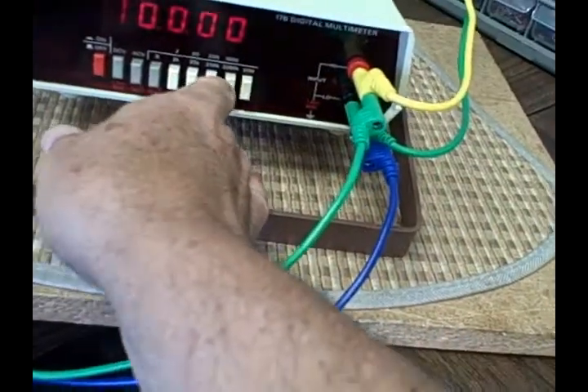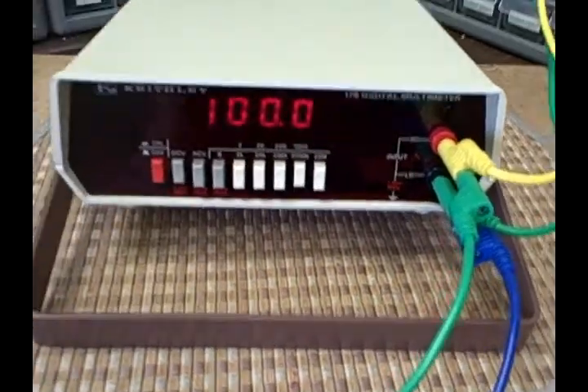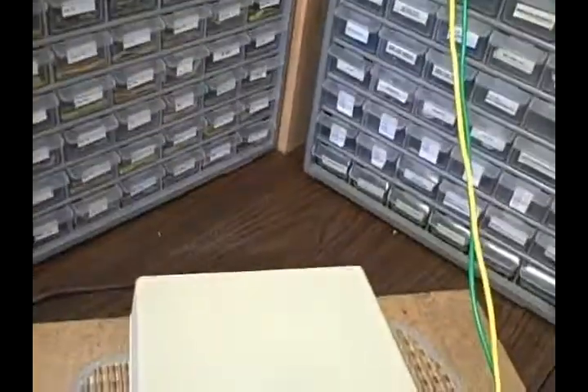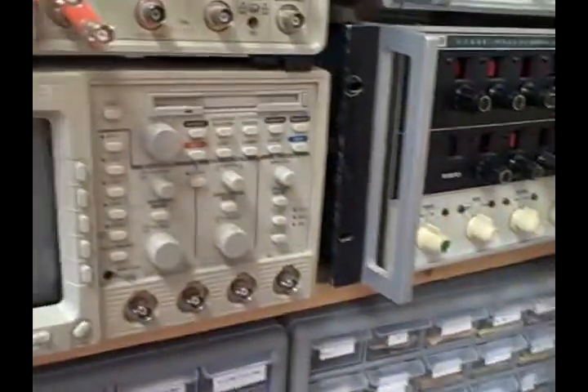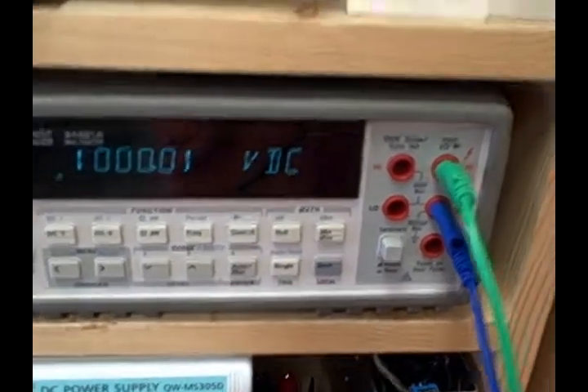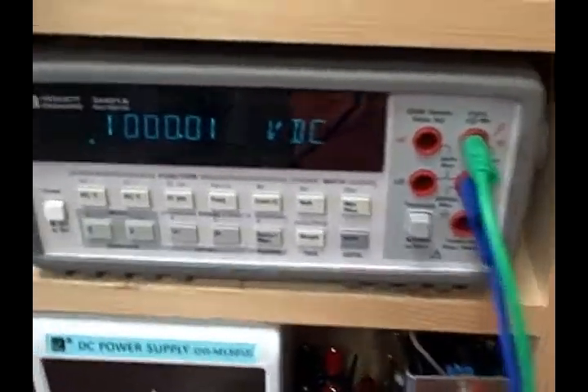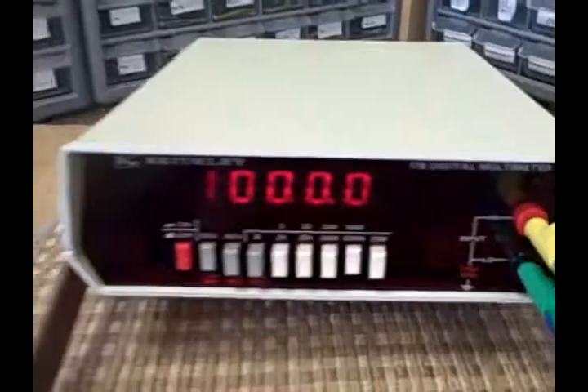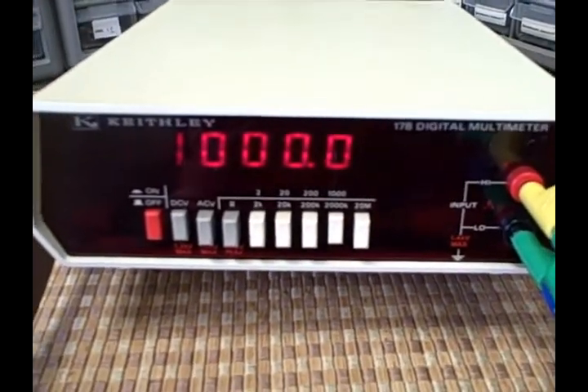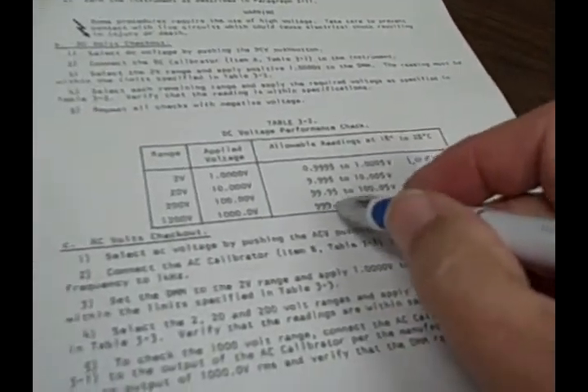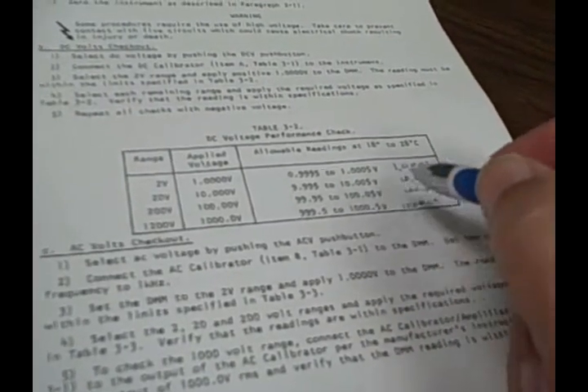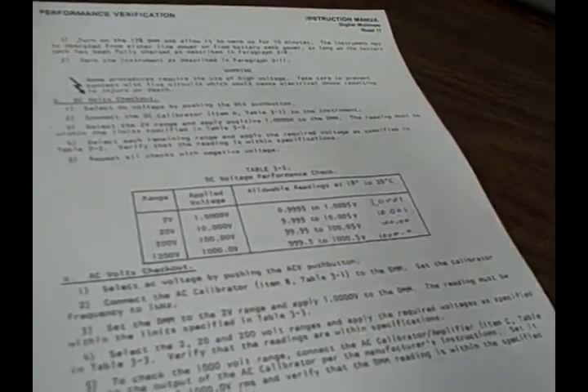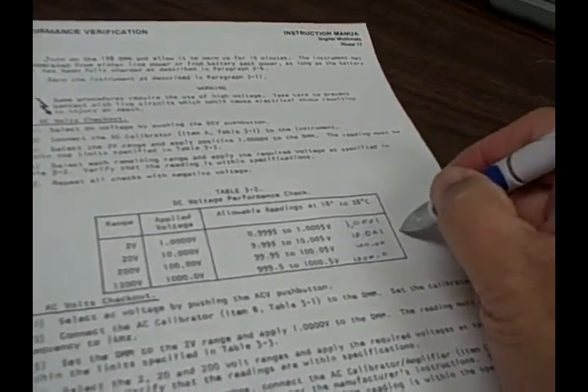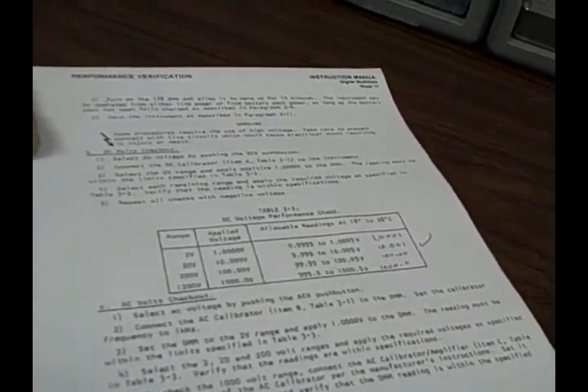Let's go to the 1000 volt scale. We have 100 volts, that's good. And we're going to take ourselves up to 1000 volts. 1000.01 on the HP. 1000.0 on the Keithley. So 1000.0, perfect. We're good if we read between 999.5 to 1000.5, and we were right on it. So we passed the DC performance check beautifully. Let's move on to AC.